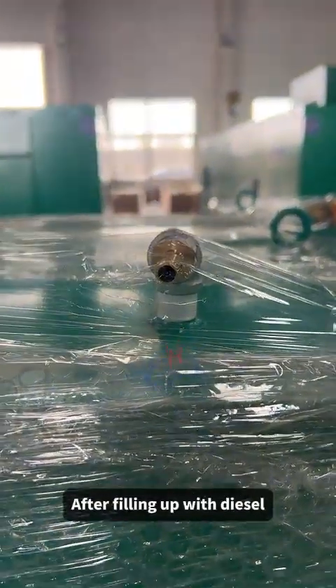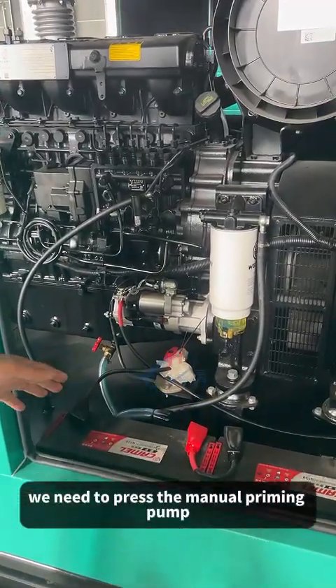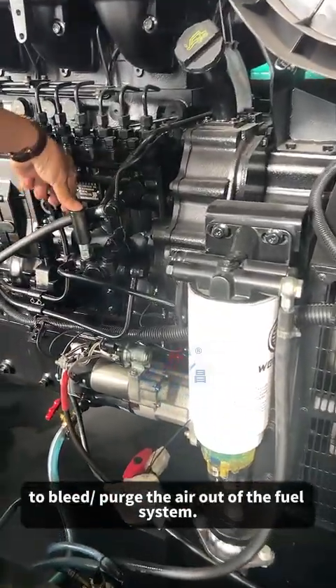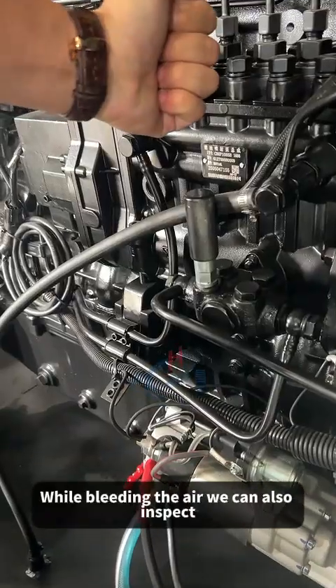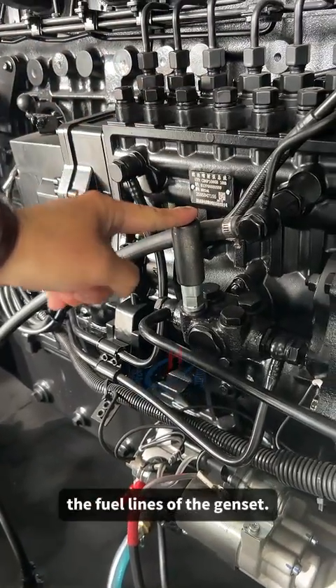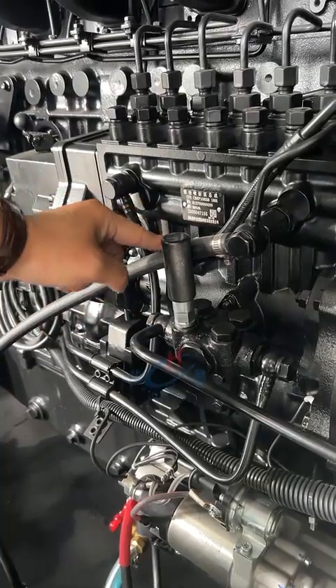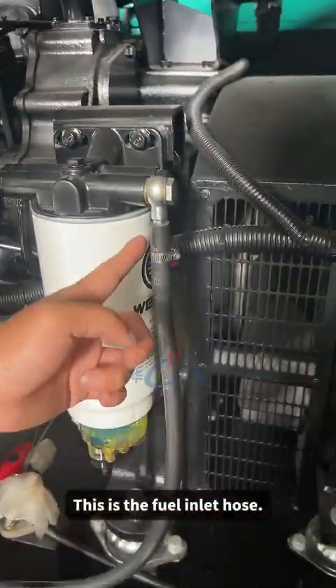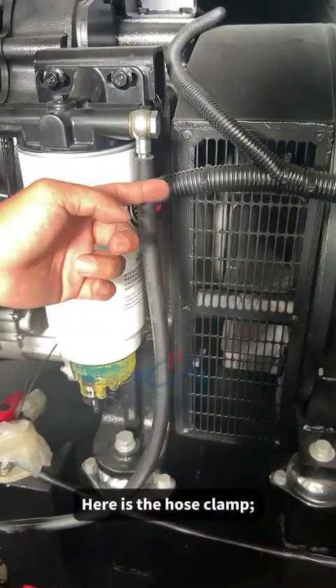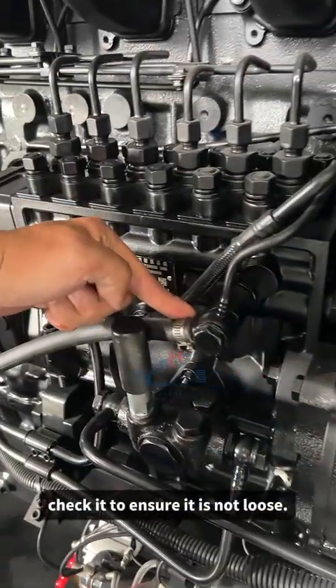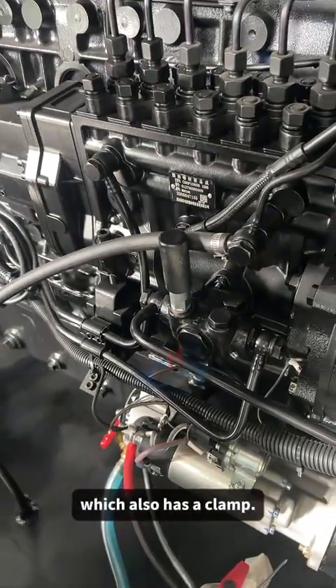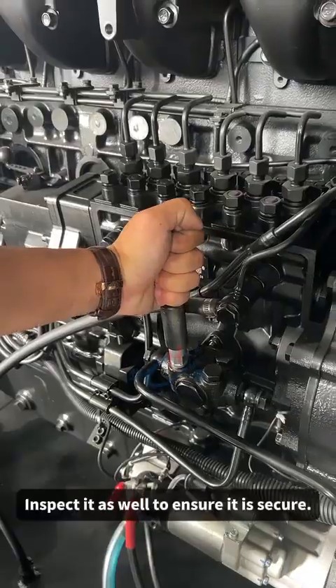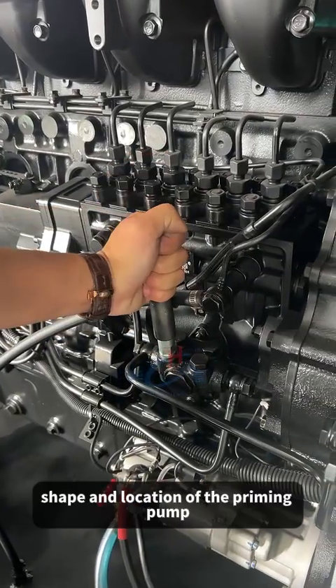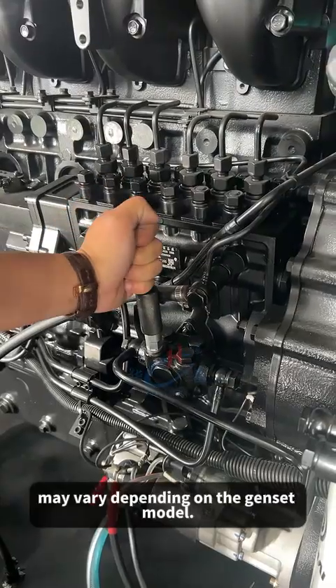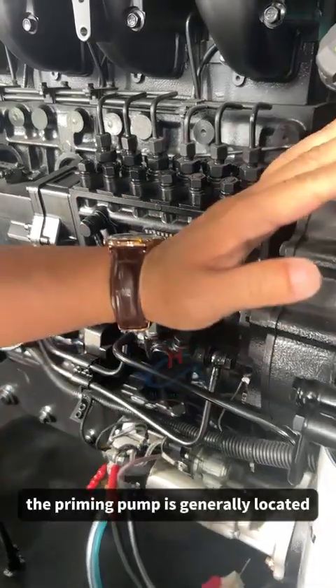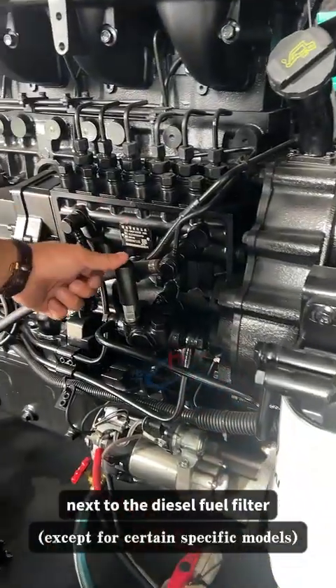After filling up with diesel, we need to press the manual priming pump, hand pump, to bleed (purge) the air out of the fuel system. While bleeding the air, we can also inspect the fuel lines of the genset. This is the fuel inlet hose. Here is the hose clamp. Check it to ensure it is not loose. This one is the fuel return hose, which also has a clamp. Inspect it as well to ensure it is secure. Of course, the size, shape, and location of the priming pump may vary depending on the genset model. However, the priming pump is generally located next to the diesel fuel filter.